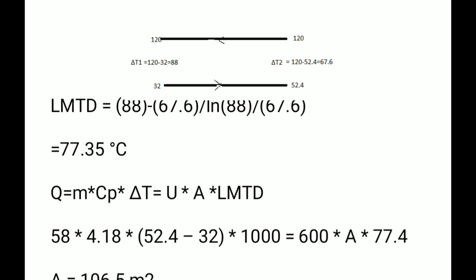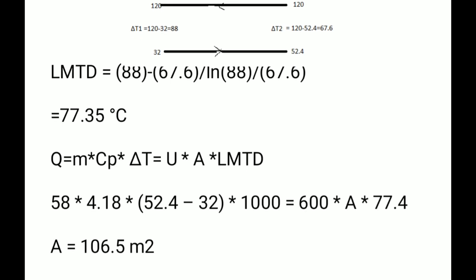Using Q = U·A·LMTD, with m·c·ΔT for the water as the heat input, U = 600 W/m²·°C, and LMTD = 77.35°C, the heat exchanger area A = 106.5 m². For any queries related to heat exchanger numericals, you can write at energyauditor2021@gmail.com. If you liked the video, please give a like and subscribe to the channel.